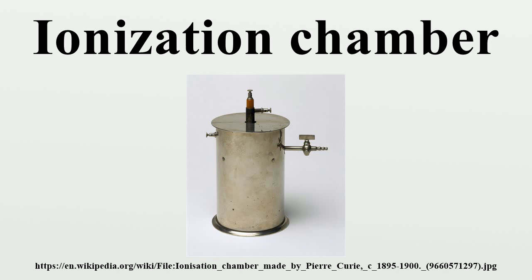This generates an ionization current which is measured by an electrometer circuit. The electrometer must be capable of measuring the very small output current, which is in the region of femtoamperes to picoamperes. Depending on the chamber design, radiation dose, and applied voltage, each ion pair created deposits or removes a small electric charge to or from an electrode, such that the accumulated charge is proportional to the number of ion pairs created, and hence the radiation dose.